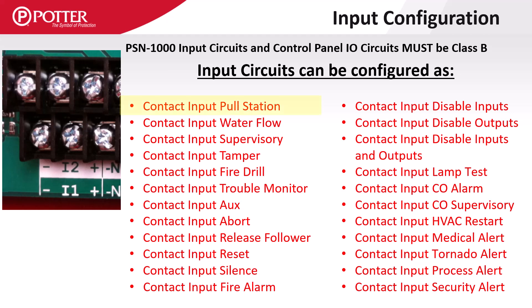The options available are: Contact Input Pull Station, Water Flow, Supervisory, Tamper, Contact Input Fire Drill — a point type used with a remote switch that initiates a fire drill — Trouble Monitor, and Contact Input Aux, a legacy point type that initiates a fire alarm condition.